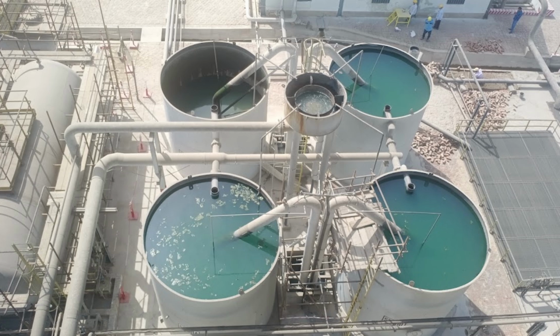So what happens when algae find these nutrients in sufficient quantities? It grows rapidly. We can observe algal bloom through the color changes in our cooling water system, and it's common in summer season. Similarly, it may also take place in winter season if we are adding more and more nitrites in our cooling water system due to ammonia ingress. We must control our nitrites in our cooling water system because these nitrites will also increase algae growth.